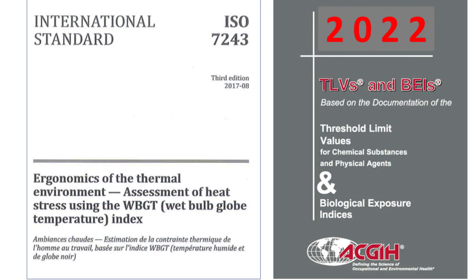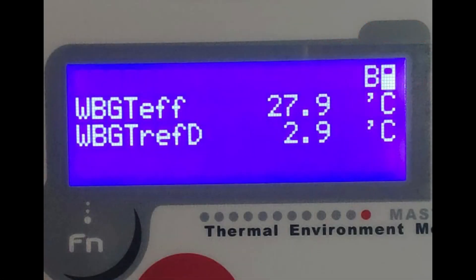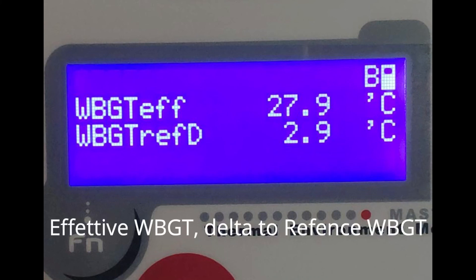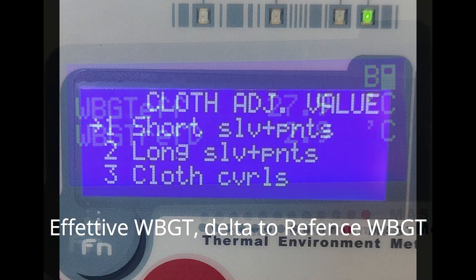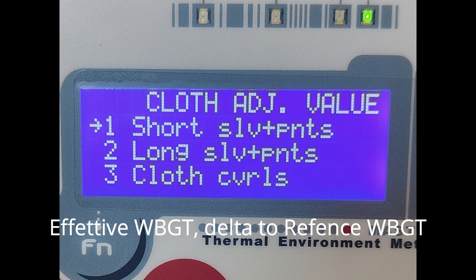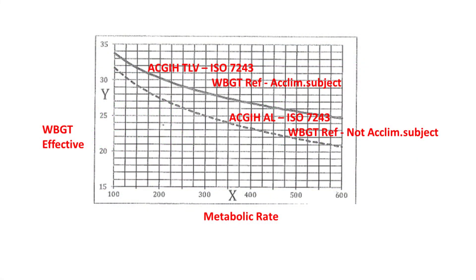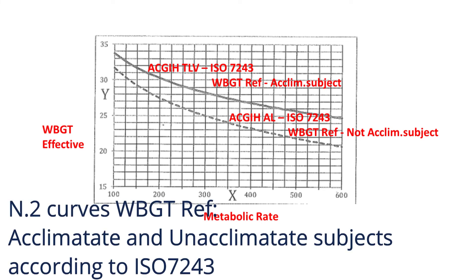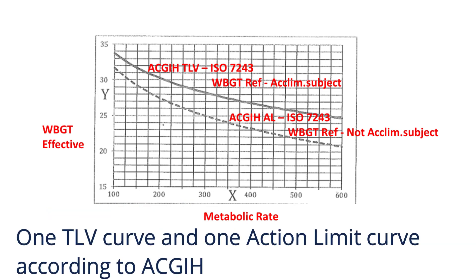According to the ISO 7243 (2017 edition) and ACGIH standards, Heat Shield produces in real-time mode the effective WBGT, which considers the clothing adjustment value, and displays the Delta to the limit — the distance between the effective WBGT value and its limit value, also called WBGT reference by ISO 7243 or TLV and action limit by the ACGIH.